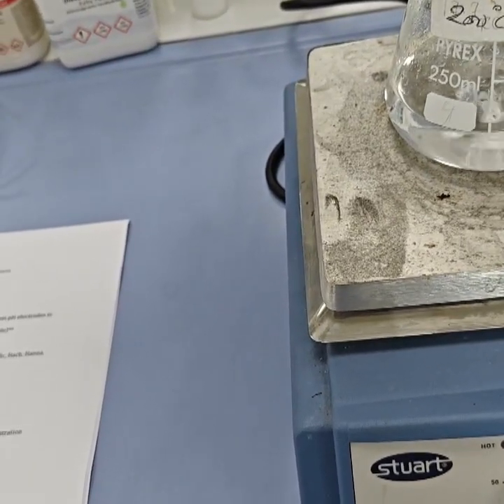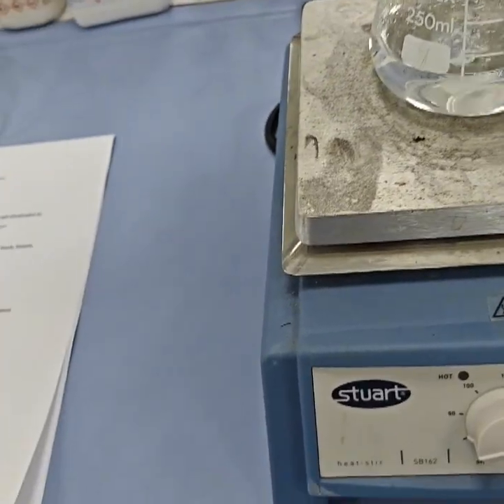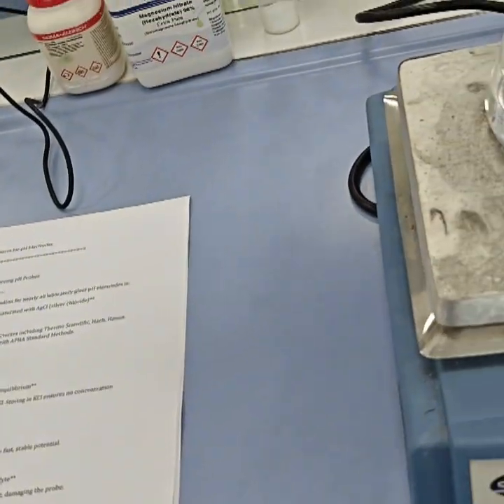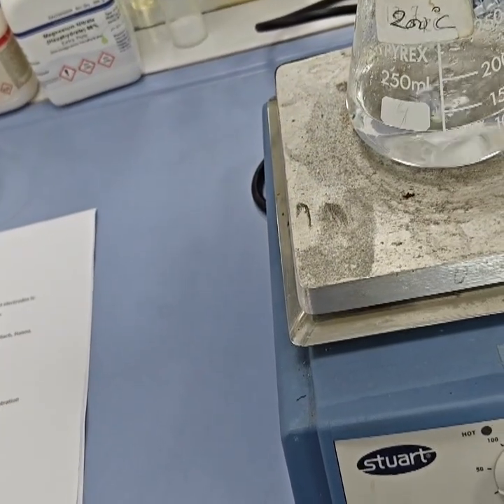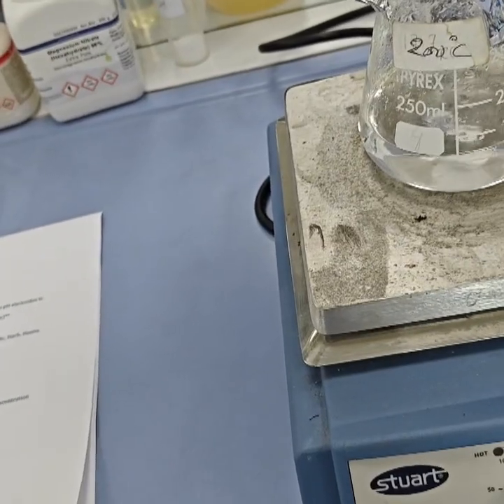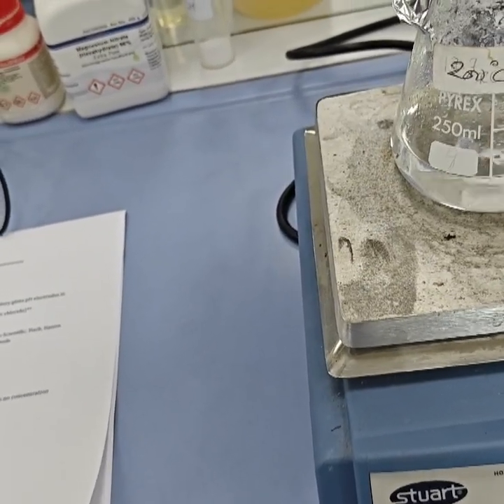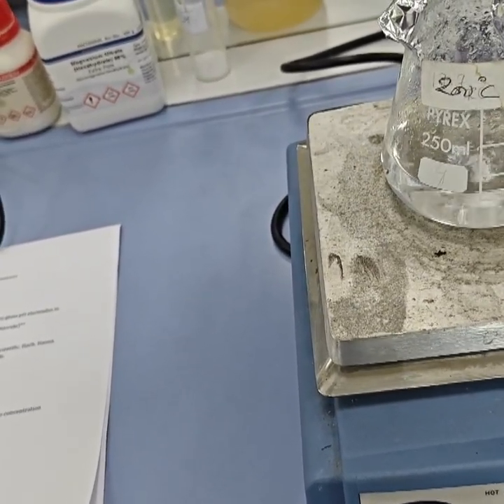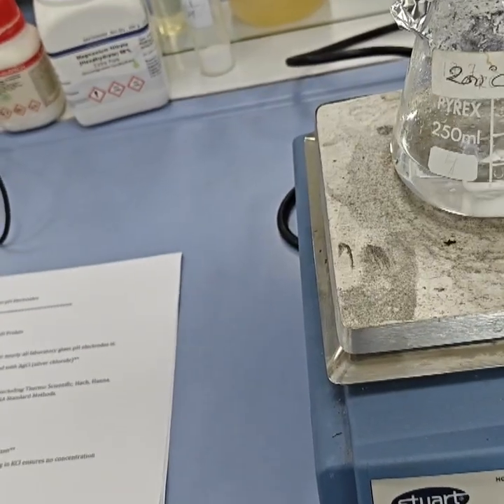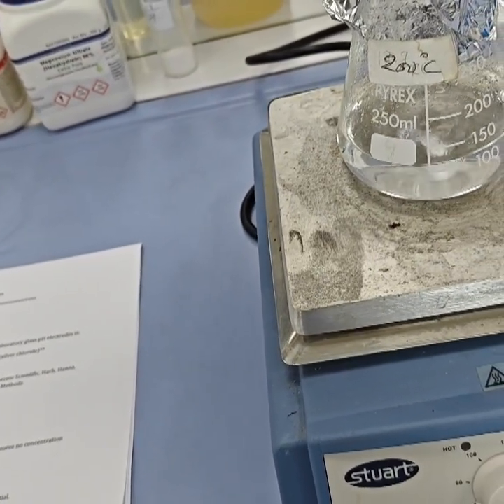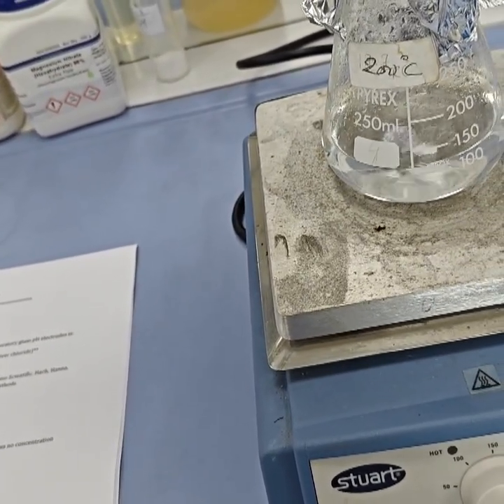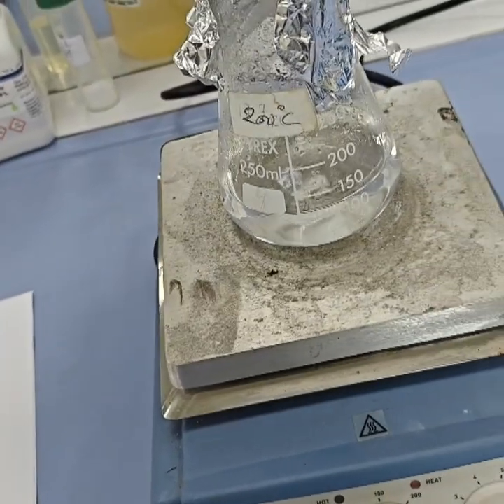The next reason is it prevents leaching of the internal electrolyte. Water or other salt solutions cause KCl to diffuse out, which will damage the probe that I am using. And the next reason is it prevents precipitation. Other salts form precipitates with Ag plus, for example calcium, magnesium, copper, blocking the reference junction.